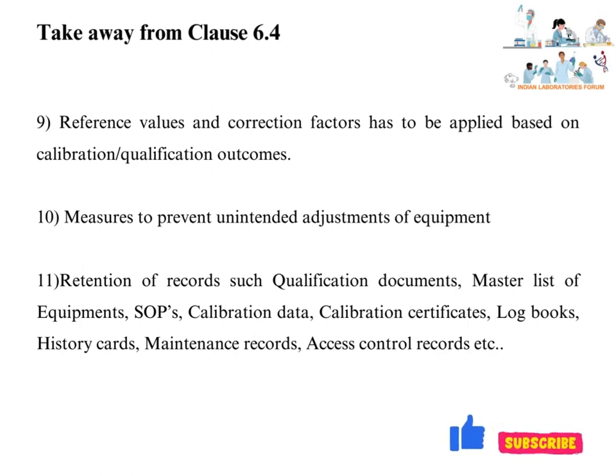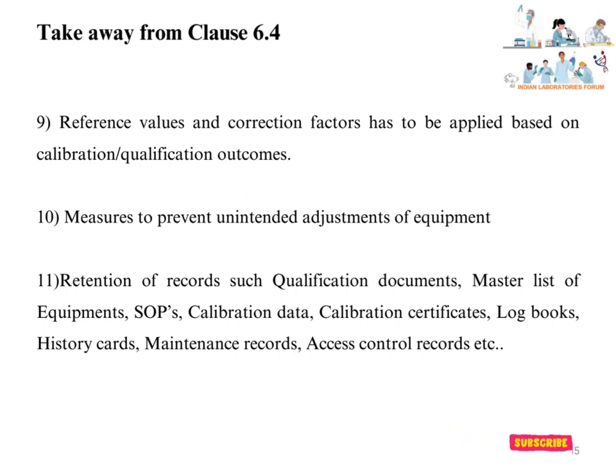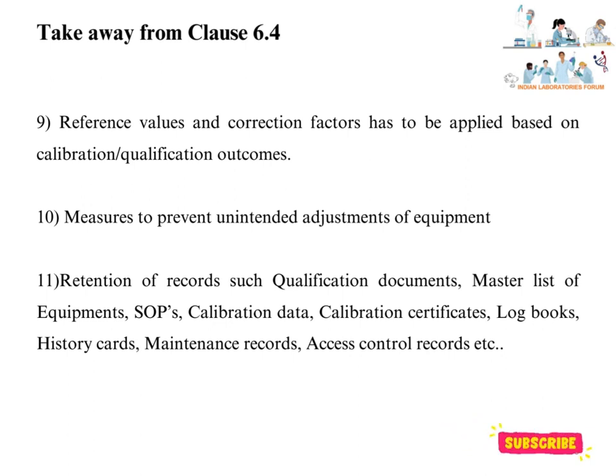Reference values and correction factors must be applied based on calibration or qualification outcomes. The lab should take measures to prevent unintended adjustments, such as access restrictions, user access privileges, user IDs, and passwords. The lab should retain records such as qualification documents, master list of equipment, SOPs, calibration data, calibration certificates, log books, history cards, maintenance records, and access control records.